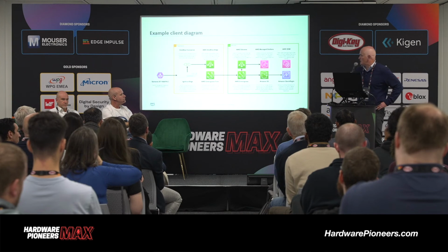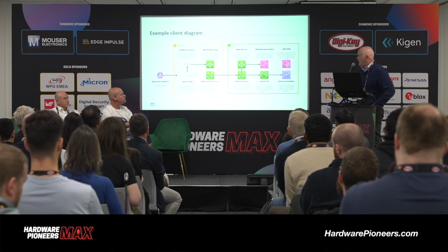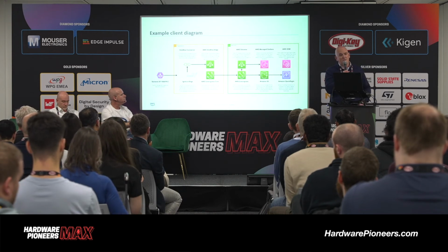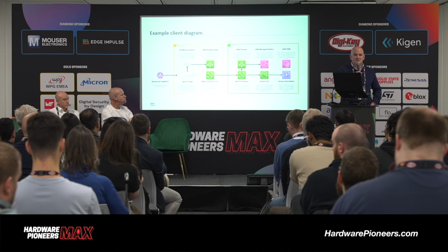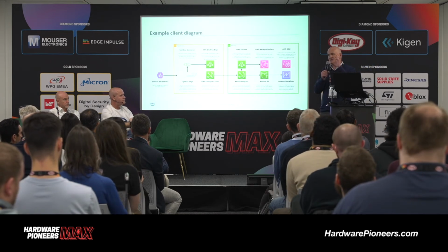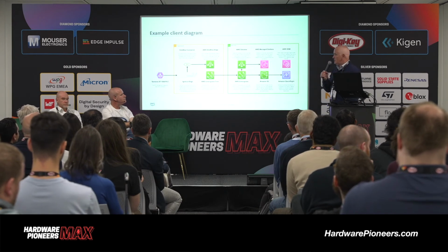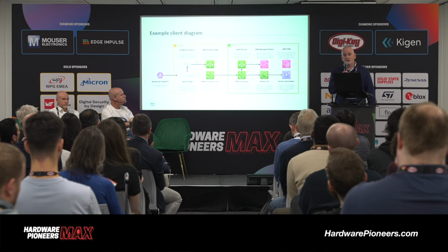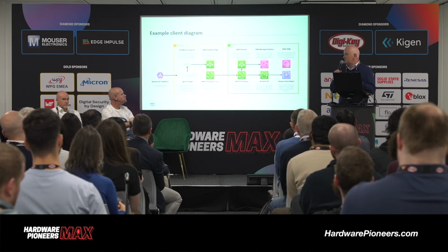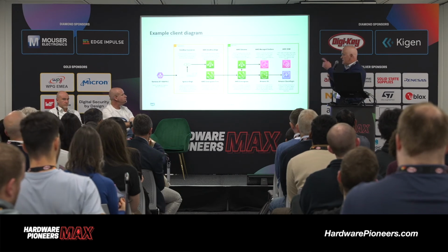We've got a few components here within each of these boxes. So the Siemens PLC itself, this is where we get the OPC UA data. So we pull that off. And unfortunately, with this customer, the way they'd actually structured that, they had created additional levels of tags. So there were nested tags within the data structure they had. So we couldn't pipe it straight into the SiteWise connector, which is typically what you can do. If it's structured, the Siemens PLC itself will normally structure it, and you could pump it straight into SiteWise.